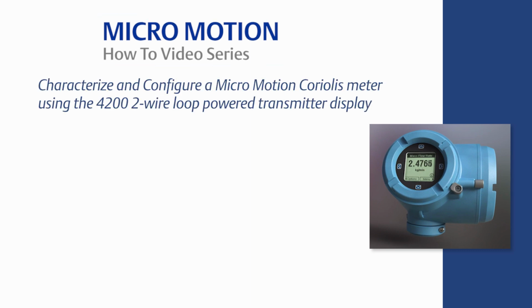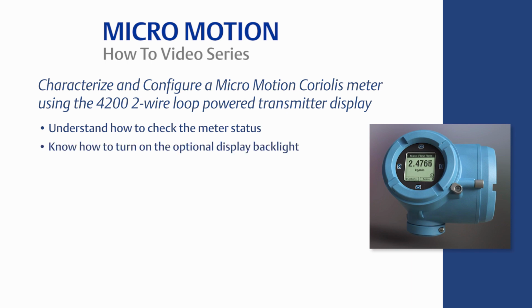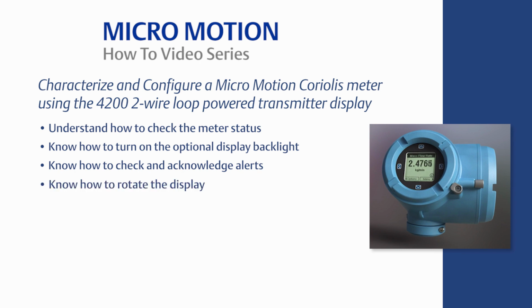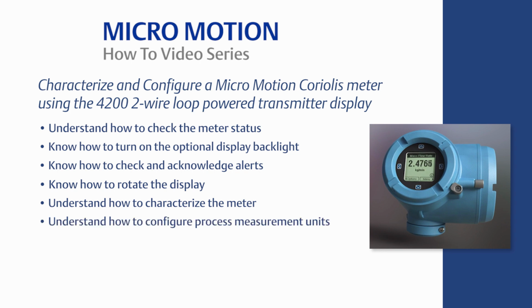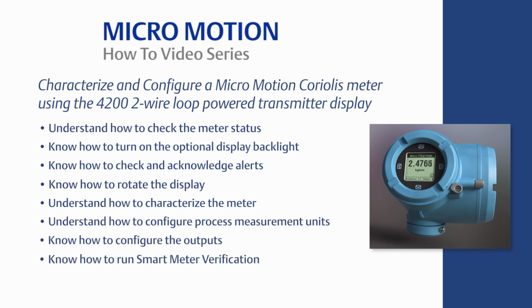This concludes the how-to video of Coriolis meter characterization and configuration using the 4200 transmitter display. In summary, when using the 4200 two-wire loop-powered transmitter display, you should now know the following. Understand how to check the meter status. Know how to turn on the optional display backlight. Know how to check and acknowledge alerts. Know how to rotate the display. Understand how to characterize the meter. Understand how to configure process measurement units. Know how to configure the outputs. And know how to run smart meter verification.